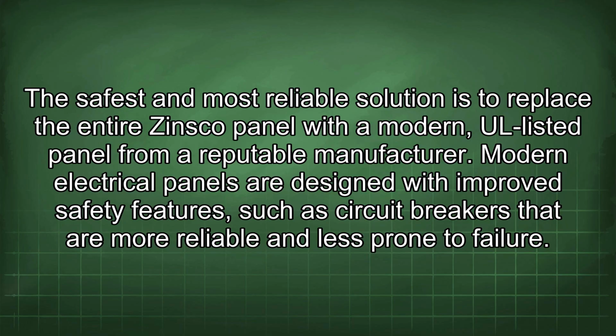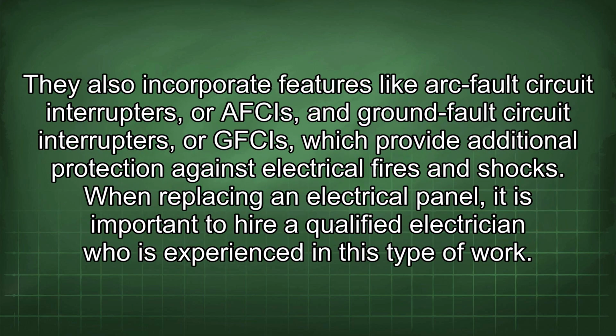The safest and most reliable solution is to replace the entire Zinsco panel with a modern, UL-listed panel from a reputable manufacturer. Modern electrical panels are designed with improved safety features such as circuit breakers that are more reliable and less prone to failure. They also incorporate features like arc fault circuit interrupters, or AFCIs, and ground fault circuit interrupters, or GFCIs, which provide additional protection against electrical fires and shocks.